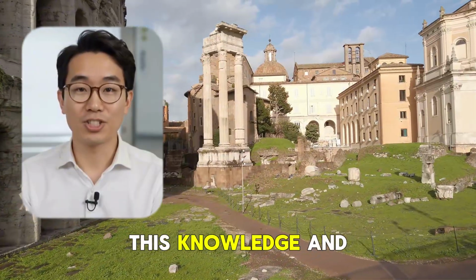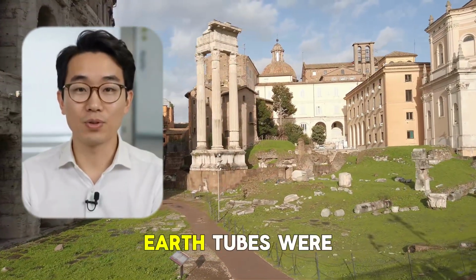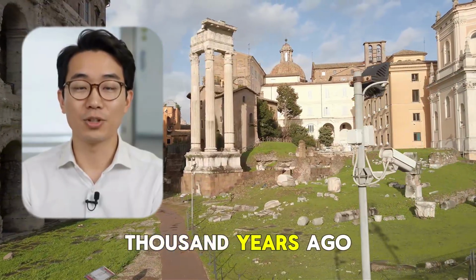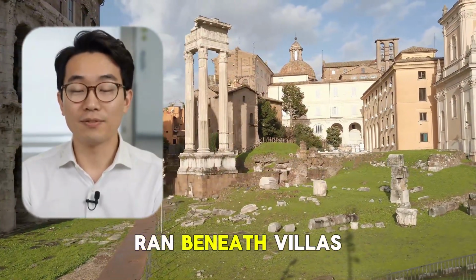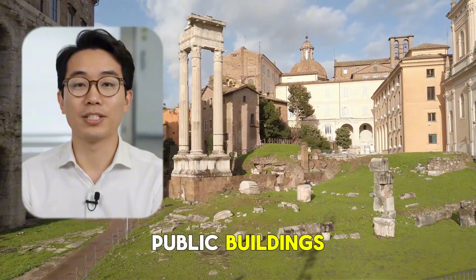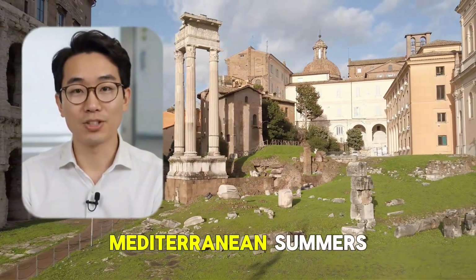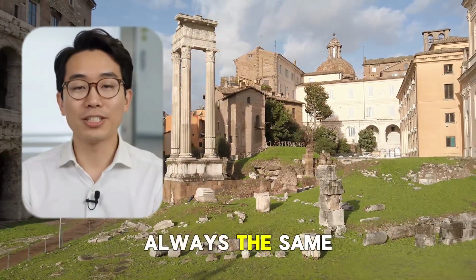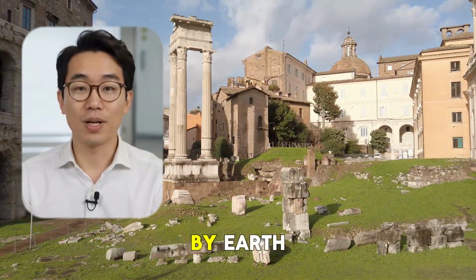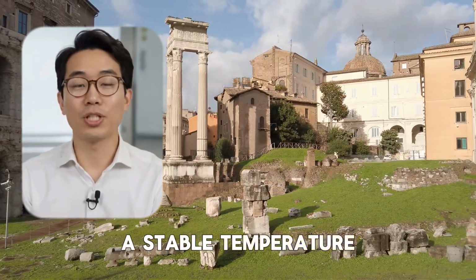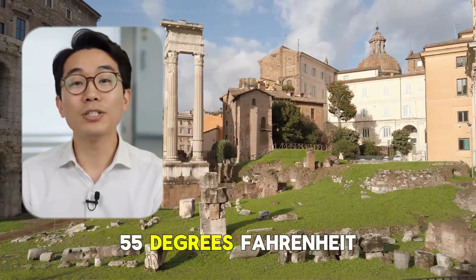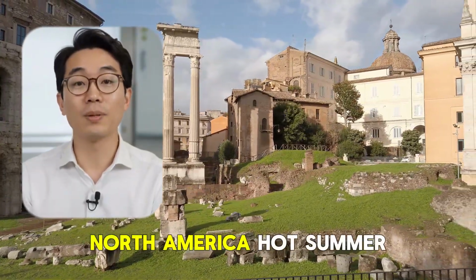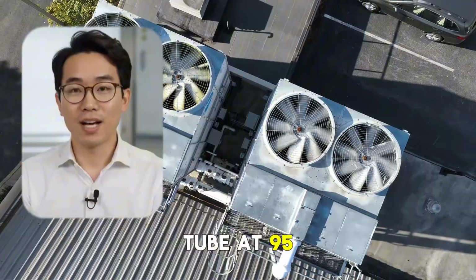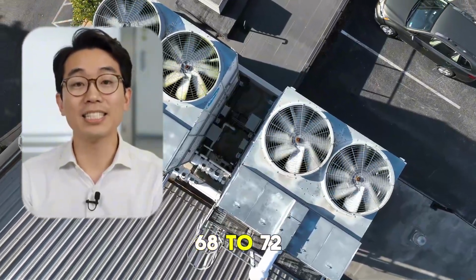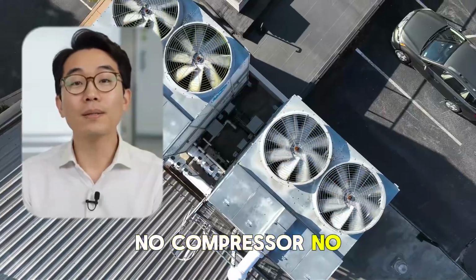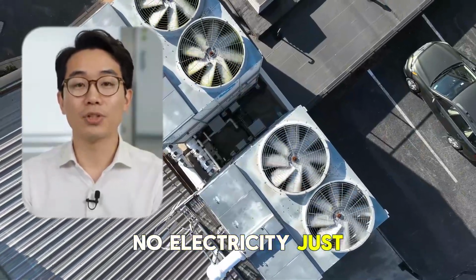The Romans took this knowledge and expanded it across their empire. Earth tubes were first used by the Romans a couple of thousand years ago. Underground air channels ran beneath villas, beneath bathhouses, beneath public buildings, keeping interiors cool through the brutal Mediterranean summers. The principle was always the same. Air passes through a channel surrounded by earth. The earth maintains a stable temperature year-round, roughly 50 to 55 degrees Fahrenheit at 6 feet of depth in most of North America. Hot summer air enters the tube at 95 degrees and exits the other end at 68 to 72 degrees. No compressor, no refrigerant, no electricity, just physics.